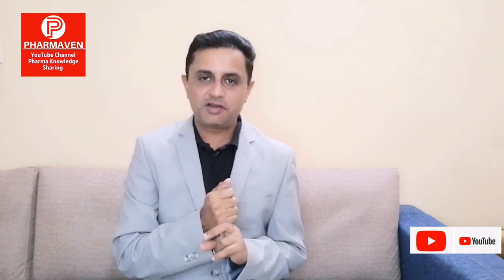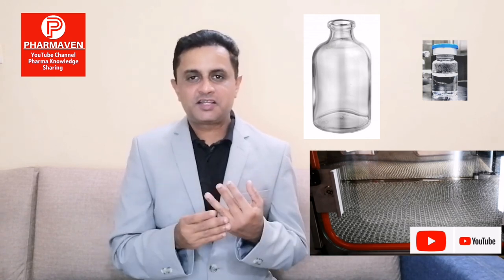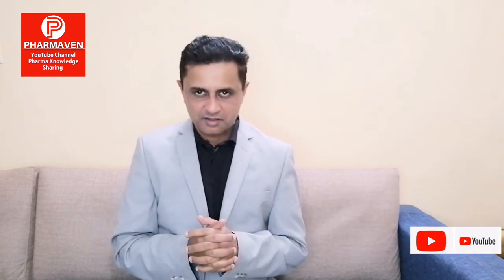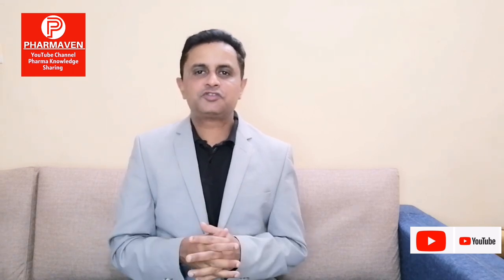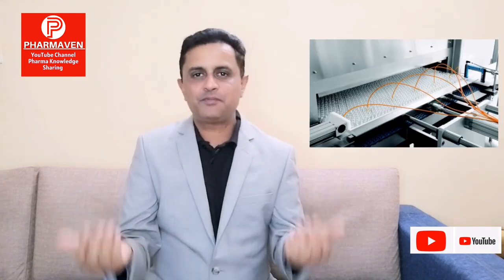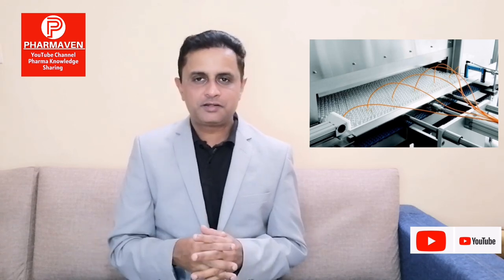First, we have to consider the smallest vial size. Second, we have to consider the largest vial size, and third will be the in-between vial size which has the most dense mass, or glass volume, glass weight inside the tunnel. So these are the three factors: the smallest vial size, the largest vial size, and the container size with the most dense mass or most dense volume inside the tunnel. This is how we have to select the container sizes. Once we decide the container size that has to be validated, then how to validate? We have to use thermocouples for temperature mapping.